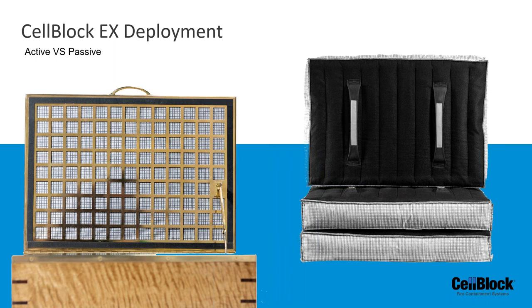And on the left, this is how it works in the cabinets and in the transport cases. The CellBlock EX is again held back with the textile, and then deployed simply by gravity. When there's an incident, the heat signature is going to burn that textile away quickly at 400F, and the CellBlock EX then, via gravity, falls and embeds and encompasses whatever is in the case or cabinet. We know how much material is deployable within that unit, and that's how we get to the rating. As long as you stay within the rating of the cases and cabinets, you'll know that you have enough CellBlock EX ready to be deployed.